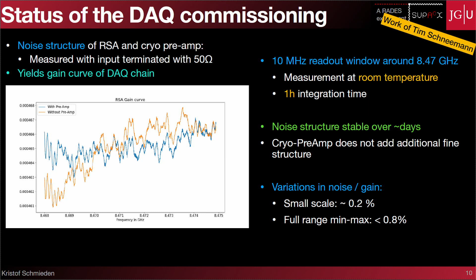So what's the performance of our readout chain? This shows the gain curve of our preamplifier in blue, the cryo preamp plus the real-time spectrum analyzer, and in yellow only the spectrum analyzer with its preamplifier. And you see quite a lot of structure here, but actually it's very small, so the small scale fluctuation is only 0.2% on the pedestal, and the full range is still below 1% on the noise pedestal of the readout chain. And this is with an integration time of 1 hour, all at room temperature at present.